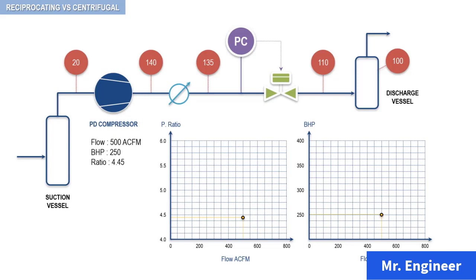Let's now assume that the control valve in the discharge process system is slightly closed. With this action, the pressure upstream of the control valve increases to 170 psi, and the discharge pressure of the reciprocating compressor increases to 180 psi. The horsepower also increases to 300 bhp. So, what has happened to the actual flow in this case? Let's plot the new pressure ratio and brake horsepower to figure it out.